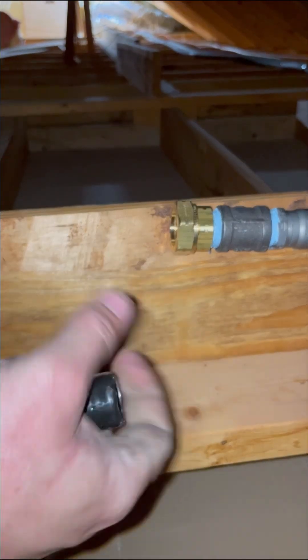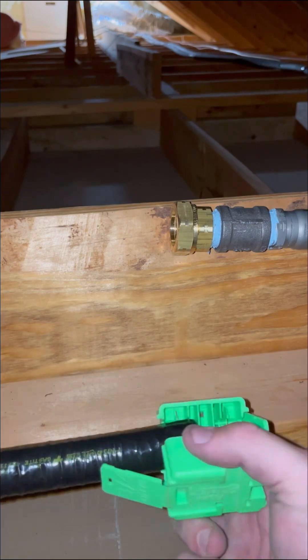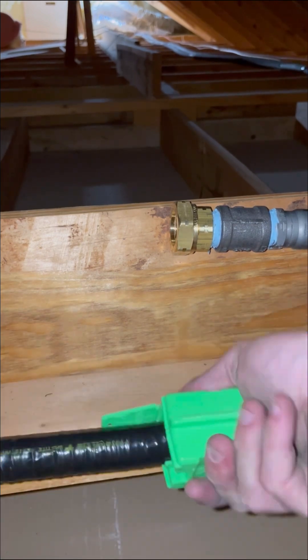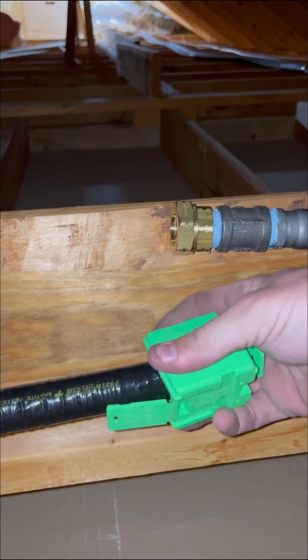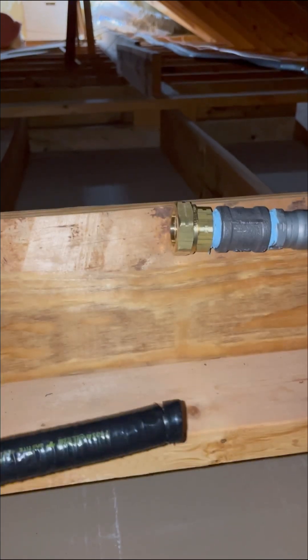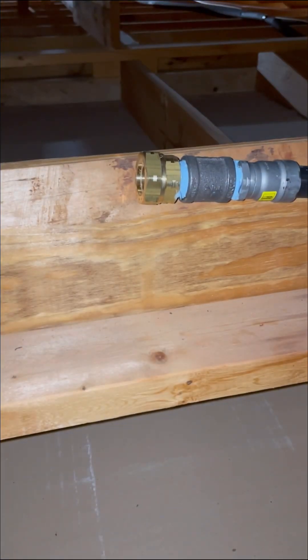All right, let's install some flexible gas piping. This is part of a larger gas job where I ran about 80 feet of gas line for a whole house generator. This was a propane system and this line was at 2 psi, which is why I'm using 3/4 piping. This flexible gas piping is manufactured by Gastite and this is their FlashShield Plus system.